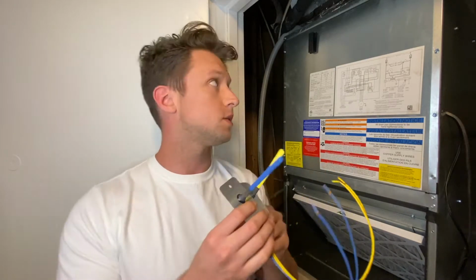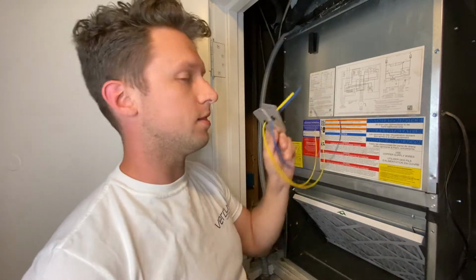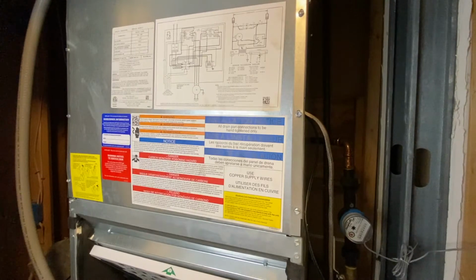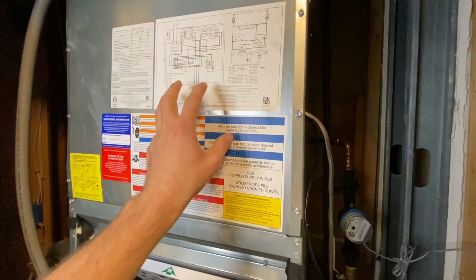These two probes come with the fan handler and go right in the supply duct. They sense the supply air temperature, which dictates your fan speed. This is the heart of the fan handler system, the control box. These wires hook up to power in your unit and also the fan wires, which I'll get into soon. The first thing we need to do is take off the cover to the motor.